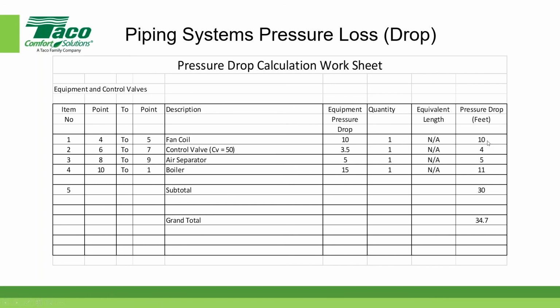And if I add that up, and let's say that's 10 and 11, that's 21, 25, 30, that's equal to 30 here, plus the 5, it actually was 4.7 in my spreadsheet, but I'll round it off. And that comes out to 34.7 or 35. So that is my calculated pressure drop for my simplified system.